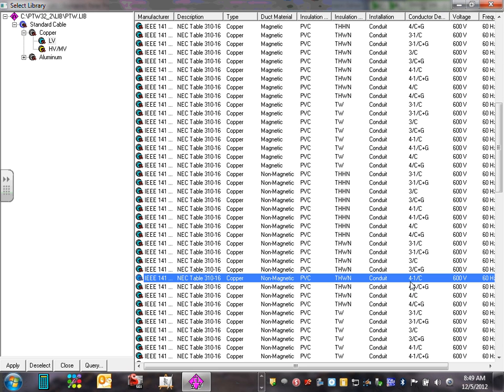We're coming underground. This and I use 4-1/C. This is how the software engineers refer to single conductor cable. So look at this. 4 means four cables. Why 4? 3-phase and neutral. And 1-C means single conductor. They are 4 single conductor cables in a big fat PVC conduit. Can I have thumbs up, Chad?